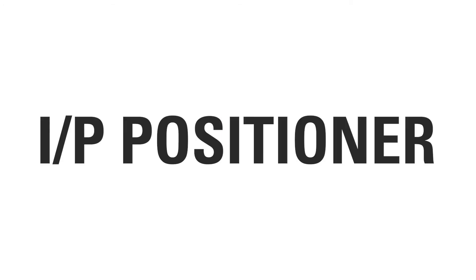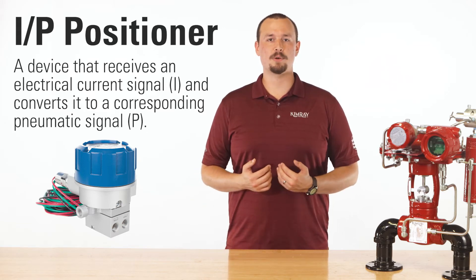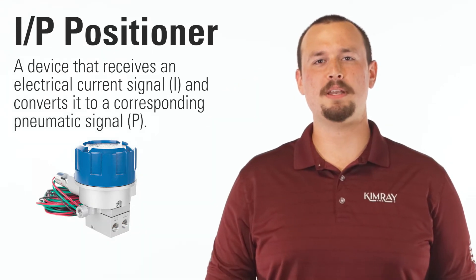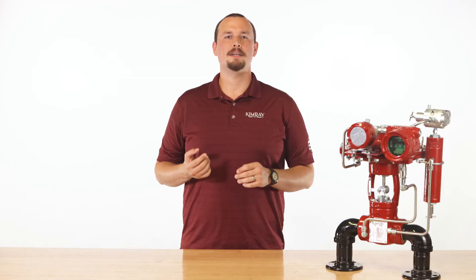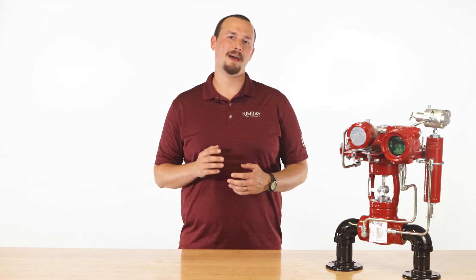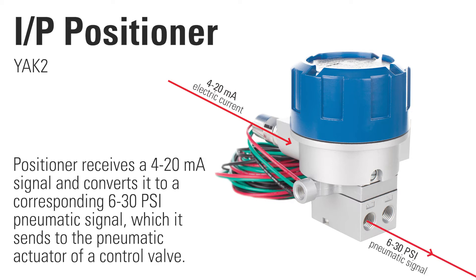The third term we'd like to go over is I/P positioner. An I/P positioner is a device that receives an electrical current signal, abbreviated I, and converts it to a corresponding pneumatic signal, abbreviated P. To do this, it also has a supply gas input that provides pneumatic pressure. For instance, our YAK2 receives a 4 to 20 milliamp signal and converts it to a corresponding 6 to 30 psi pneumatic signal, which it sends to the pneumatic actuator of a control valve.